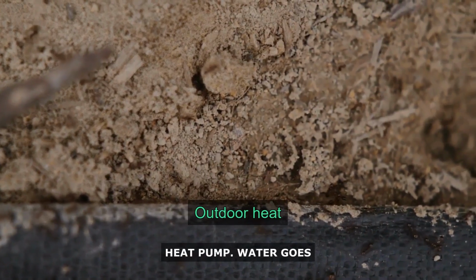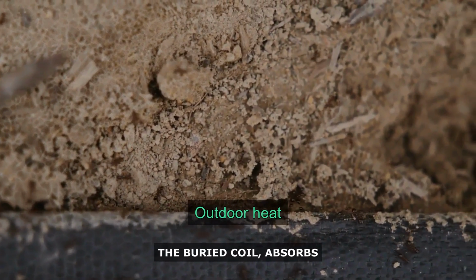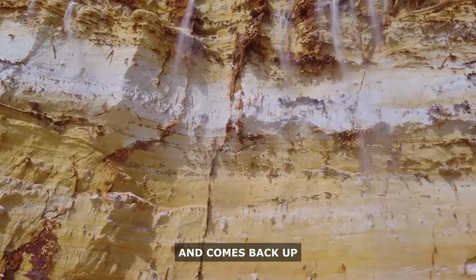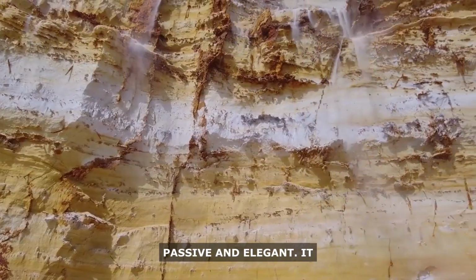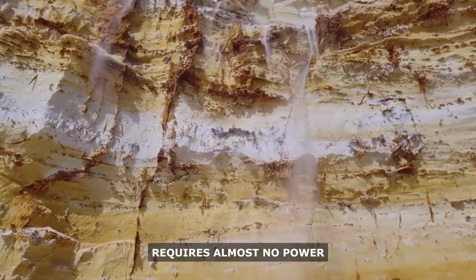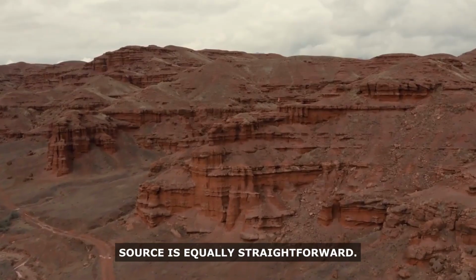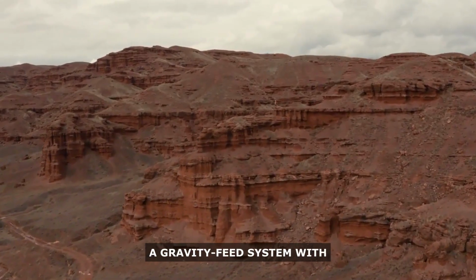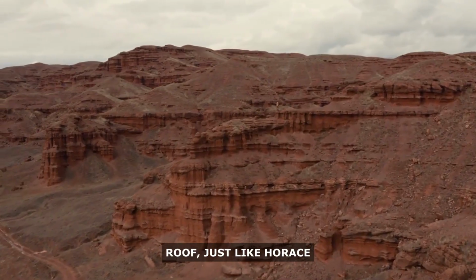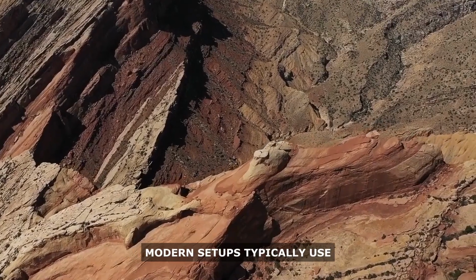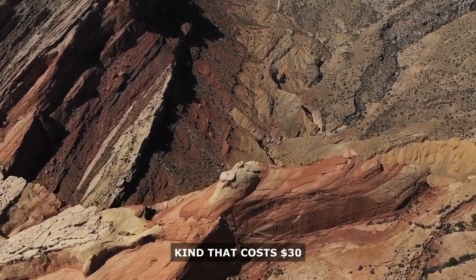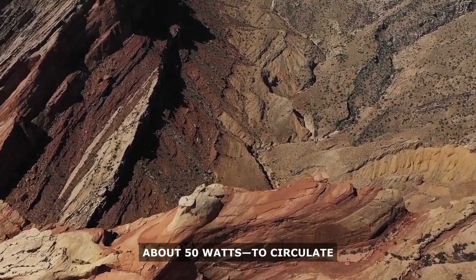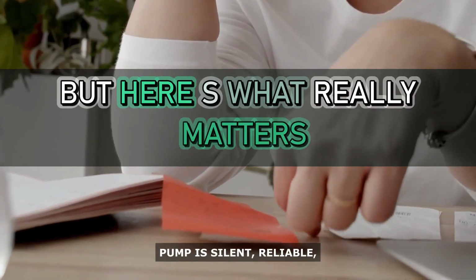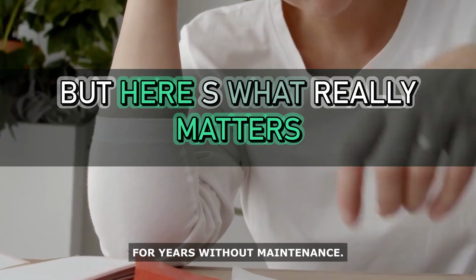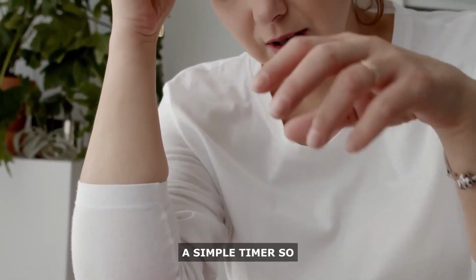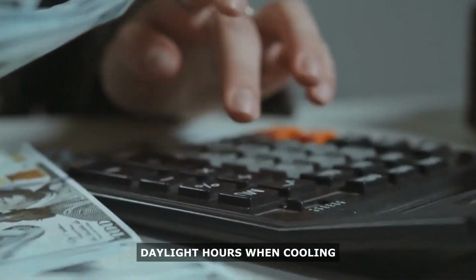The water source is equally straightforward. Some older installations use a gravity feed system with a barrel on the roof, just like Horace Tatum used in 1926. Modern setups typically use a small submersible pump, the kind that costs $3 to $5 and uses about 50 watts, to circulate the water continuously. The pump is silent, reliable, and designed to run for years without maintenance. You wire it into a simple timer so it only runs during daylight hours when cooling demand is highest. At night, when the temperature drops, you let the natural convection do the work, or you run the system at lower speed to refresh the water temperature without working as hard.